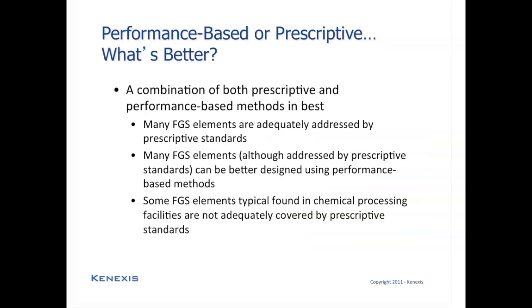So one would often ask, well, which approach should I use? Should I use the performance-based approach, where I simply analyze the risk and apply as much instrumented safeguards as are required to mitigate that risk? Or do I follow a completely prescriptive approach where I just follow a rule set and check off the numbers as they are completed? Well, in reality, it's best to use a combination of both prescriptive and performance-based methods.